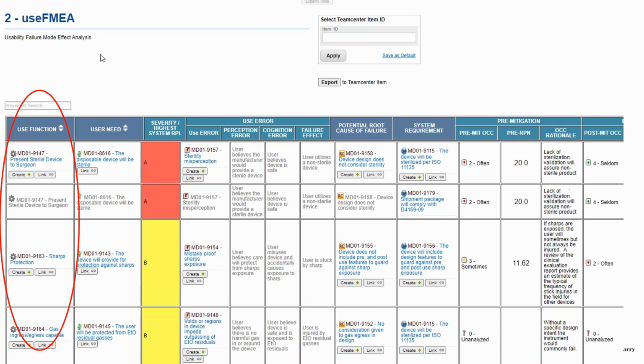So just to provide you with that traceability, because in the past, what we've talked about is this progression that happens, and there's a negative view of the design, which is really what this risk analysis is. We're building out user needs and identifying use errors in a way that allows us to create a set of system requirements that are the result or the deliverable out of the risk analysis. This is really all about assuring that we don't have failure of the sterility of the device. That's a very different question than saying, do we need a device that's sterile? If it's sterile, how are we going to provide that sterility to the patient, right?